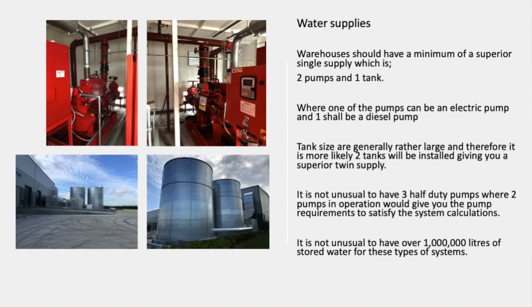Okay. So the tank sizes seem to be rather large. So the reason for splitting into 2 is because it can be more economical to have 2 tanks rather than one big huge tank. The ones on the left are 562 cubic metres each. So there's over 1 million litres of water there. And if you're combining both of the tanks, it would take up a huge surface and it'd be quite high too. This one in particular was next to an airport, so we were limited to the height of the tanks also. Okay. But it's not unusual to have 3 half duties, where 2 of the pumps in operation will give you the duty of 1 of the pumps. It's also, as I say, not unusual to have over 1 million litres of water in a warehouse system.